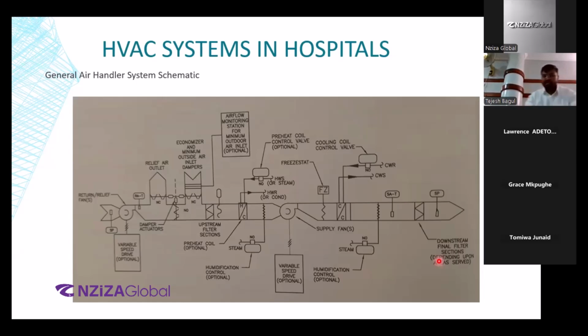All right. So over here, as you see, this is where the supply air is moving into the area, right? This is where the return air is coming back to the air handling unit, right? We have a relief so that we do not over pressurize an area. And then you have the outdoor air coming into the air handling unit, right? What goes out of here is the minimum total ACH. What comes in from here is minimum outdoor ACH. So the total ACH will be a combination of the return air and the outside air. Is that making sense? Okay.